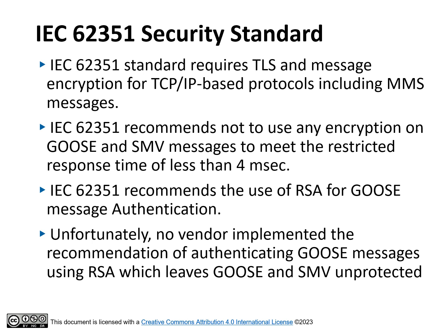The IEC 62351 standard requires TLS and message encryption for TCP/IP-based protocols, including MMS messages. IEC 62351 recommends not to use any encryption on Goose and SMV messages to meet the restricted response time of less than 4 msec.